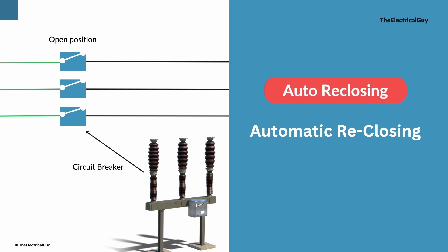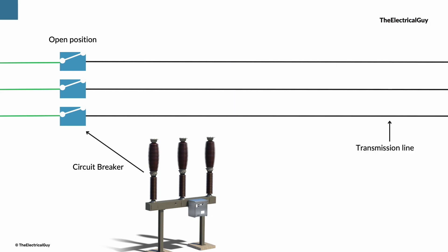In the early days, line operators soon realized that when an overhead line tripped out of service, in the majority of the cases the fault was transient in nature. And this scenario is true for 90 to 95% cases.